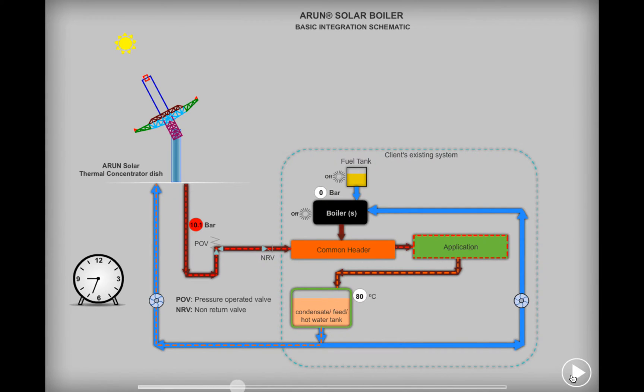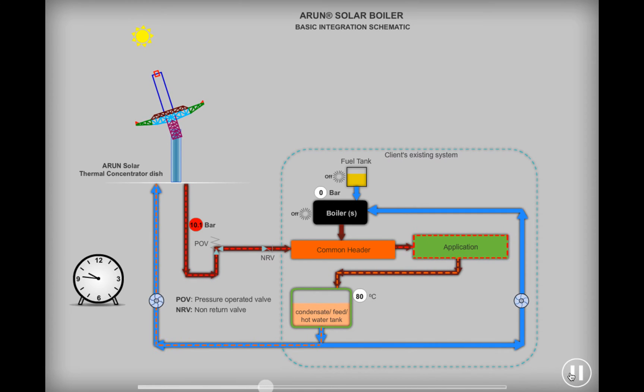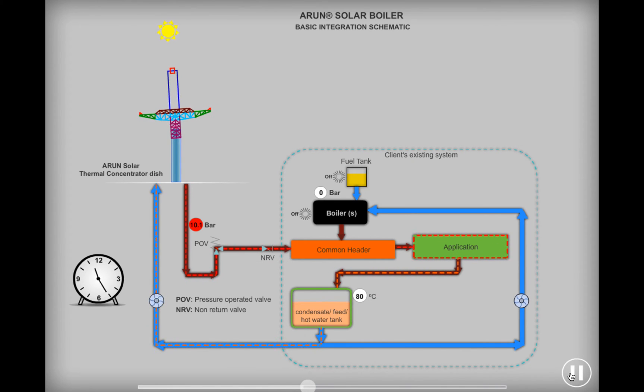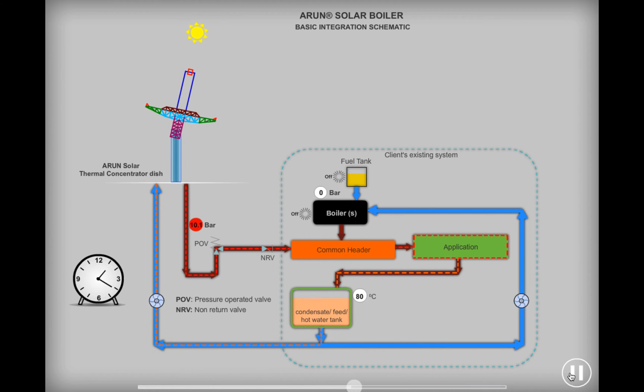As a result of the steam delivery by the Arun solar boiler, the existing boiler will automatically switch off and stop consuming any fuel. In case the quantity of steam required by the various applications is higher than the steam delivered by Arun, the existing boiler will deliver the balance steam requirement. Since the quality of steam from the solar boiler is the same as that delivered by the conventional boiler, from the process or application perspective it will not make any difference as to which boiler is delivering the steam.